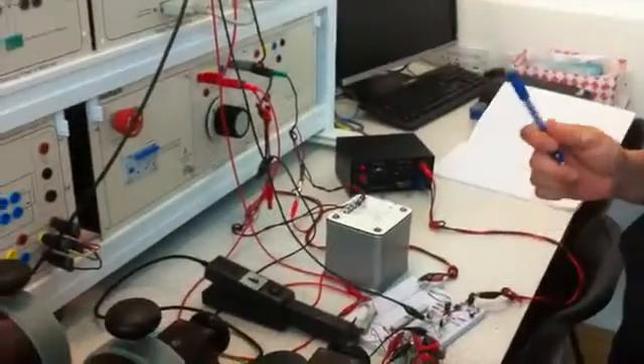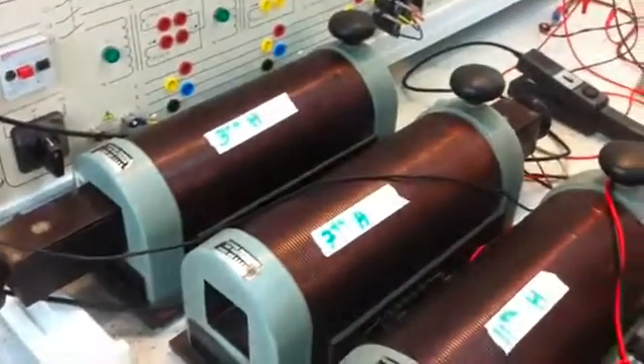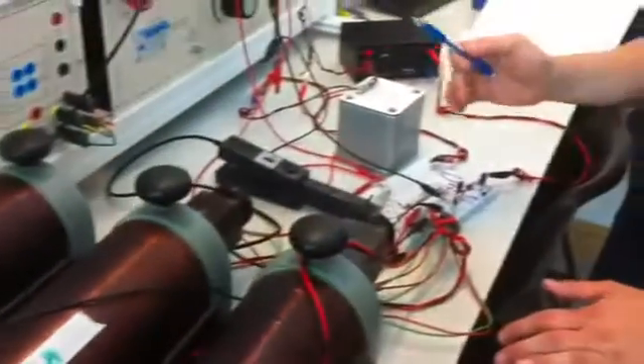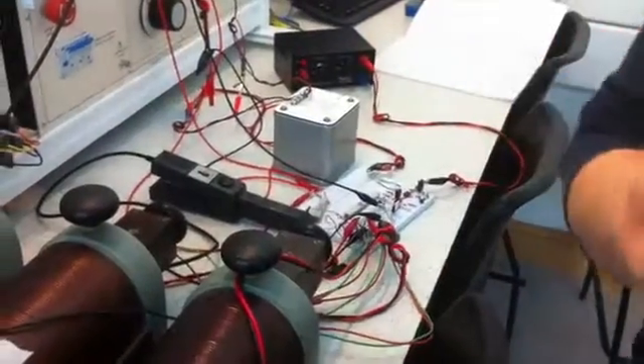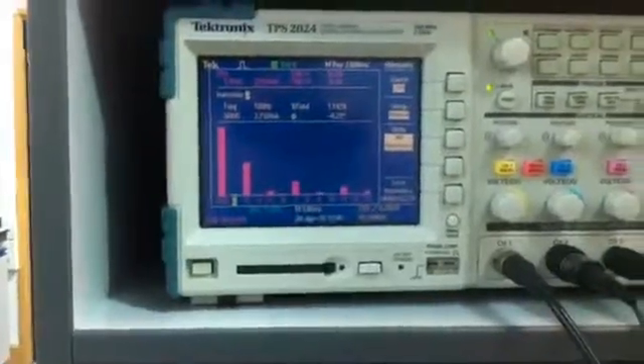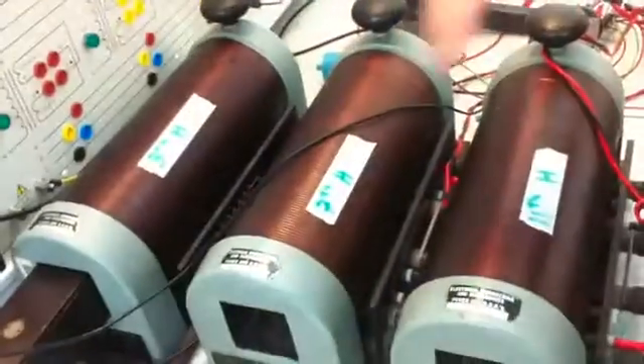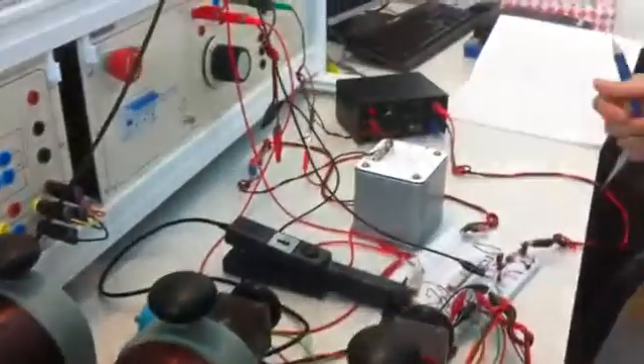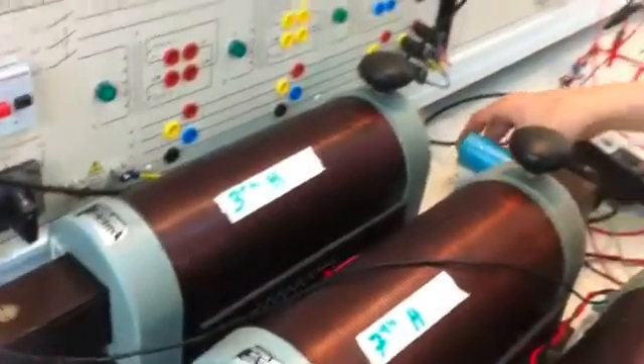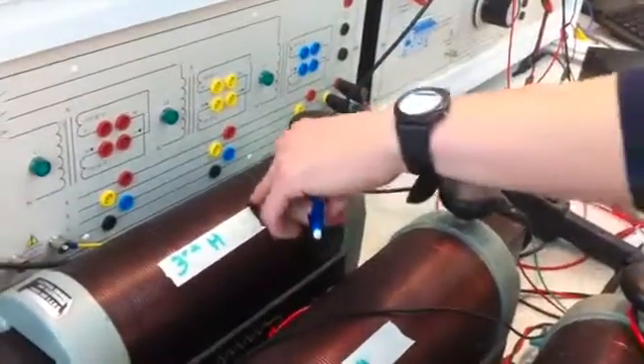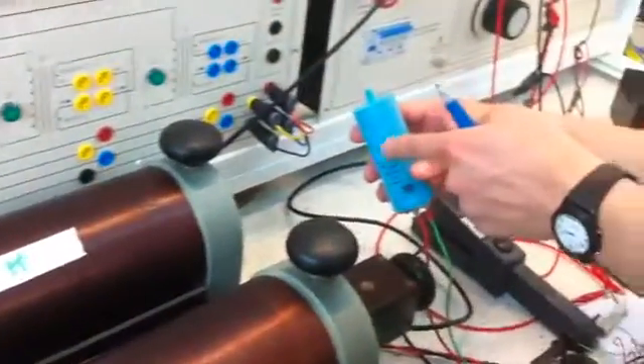All right, I'm now going to explain how I'm going to add the filters, the parallel passive harmonic filters, across the nonlinear load in order to mitigate the current harmonics, which you can see over here. So these are the current harmonics I'm going to be mitigating by applying these passive filters which I've designed. The first one that I'm going to apply is for the lowest harmonic, which is the 3rd harmonic. And the way I do that is by putting this inductor here in series with this capacitor, which is then in parallel over the nonlinear load.